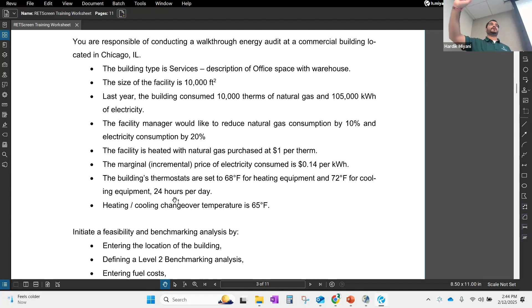So I will go into the schedule. That is the place: my heating is at 68, cooling is 72, and my changeover temperature, they have given, is 65. The meaning of changeover temperature is what ambient temperature my system changes from heating to cooling mode or cooling to heating mode. Ideally it is in the range of 60 to 65. The way we determine it, there needs to be a detailed utility bill analysis done, but for now we will assume it is 65.